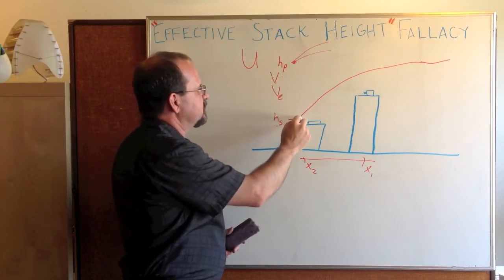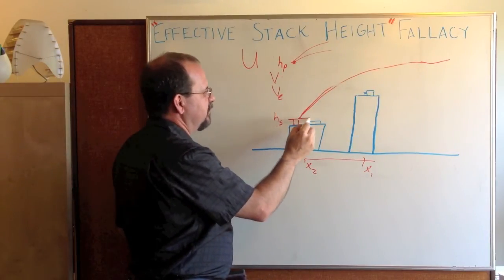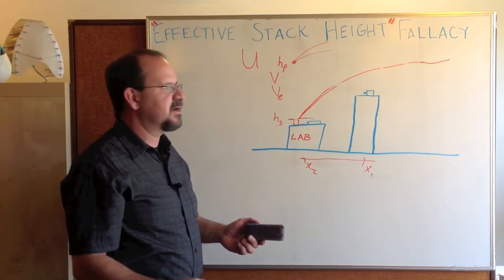For example, this is kind of a low wind speed plume rise case, but if you have high wind speed, you get very little plume rise. You could end up with a lot of re-entrainment at a nearby air intake.